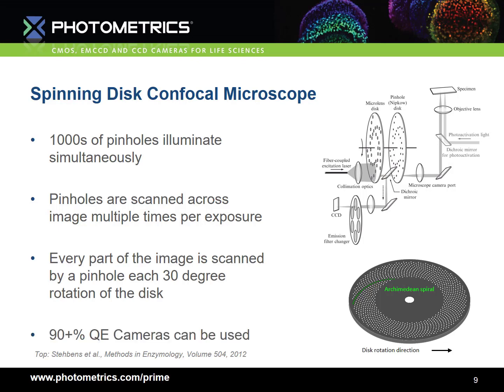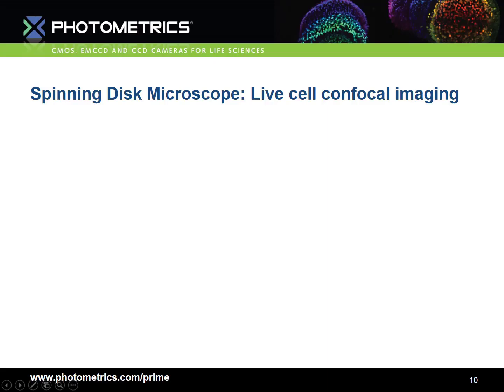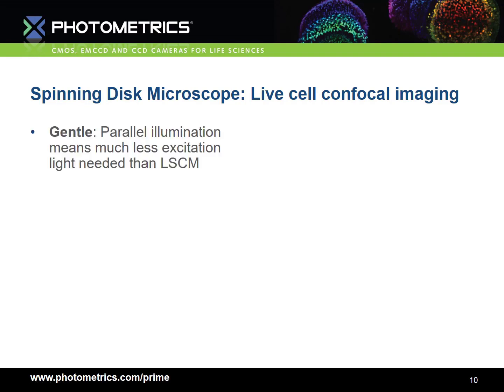Another key advantage of scanning in parallel is that we no longer have to use very inefficient photomultiplier tubes. We can instead use really high quantum efficiency cameras. The quantum efficiency of a photomultiplier tube — the number of incident photons that are converted into electrons — can be as low as 10 or 15 percent. For modern camera technology, that's in excess of 90 percent. The result of this parallelization is a technique that's much more gentle. Much less excitation light is needed than laser scanning confocal microscopy, and that light itself is much less concentrated, meaning that photobleaching is slightly mitigated.